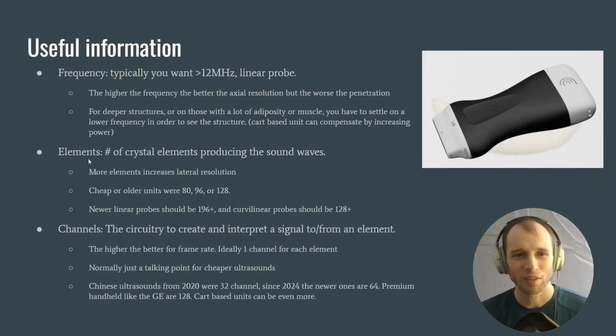But what are the elements? These are the number of PZT elements producing the sound wave. More elements improves resolution. Cheaper or older units were 80, 96, 128. Newer linear probes should be 192 or greater. Curvilinear probes should be 128 or greater.